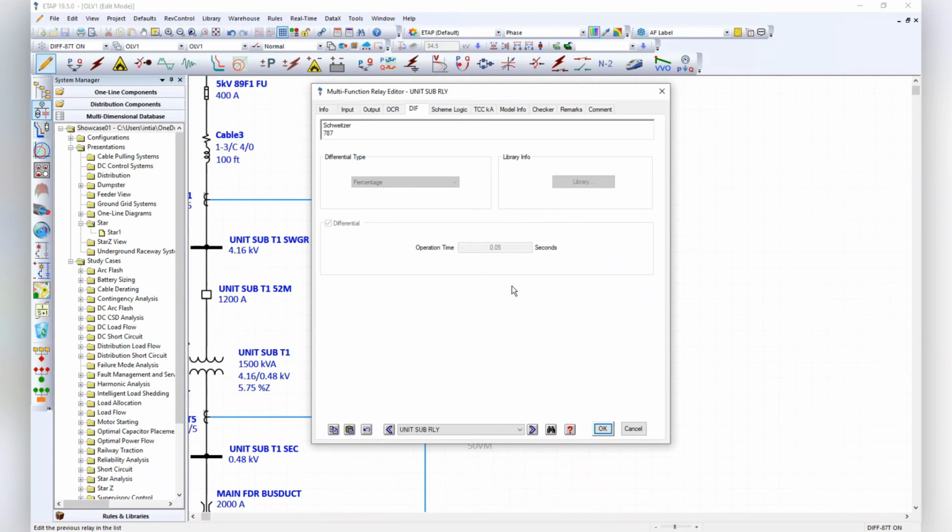Here on the 787 on the other side, I'm setting up about 3 cycles, and that is the worst case, but as you can tell, it's a little bit slower on processing time. It could be faster. If it's on restraint, it can be up to 2 cycles per the specs on the 787.